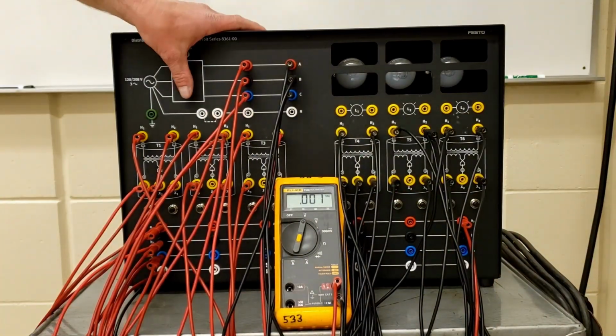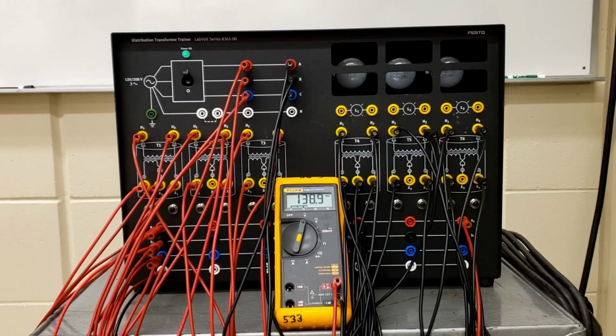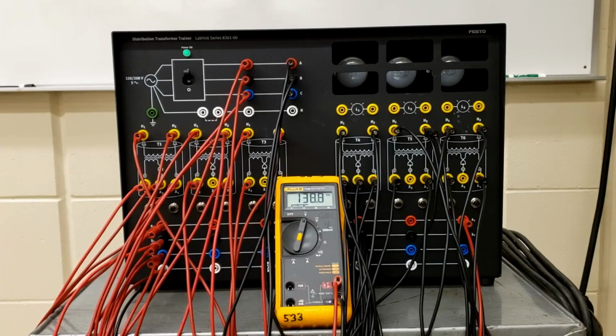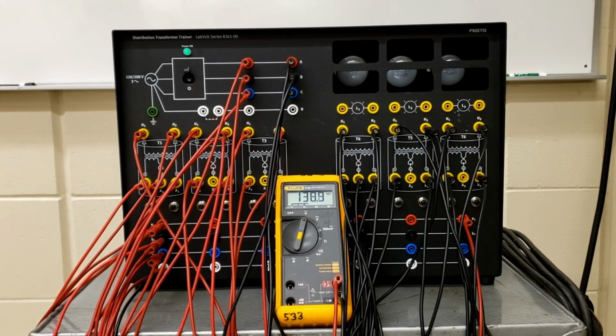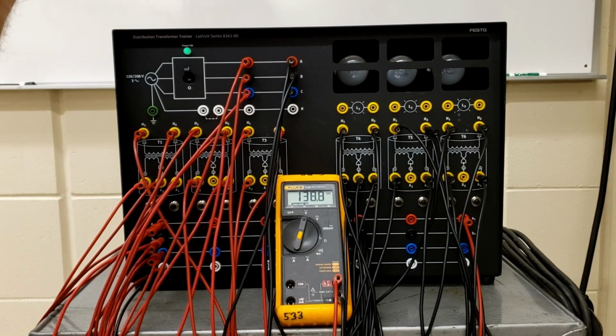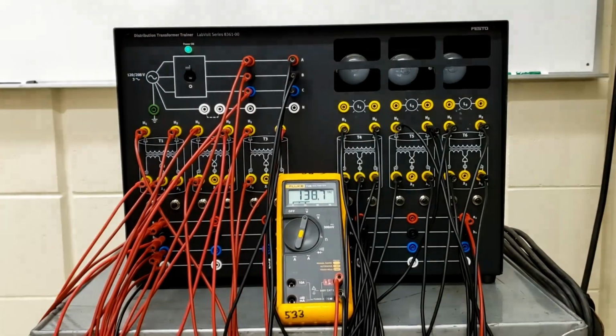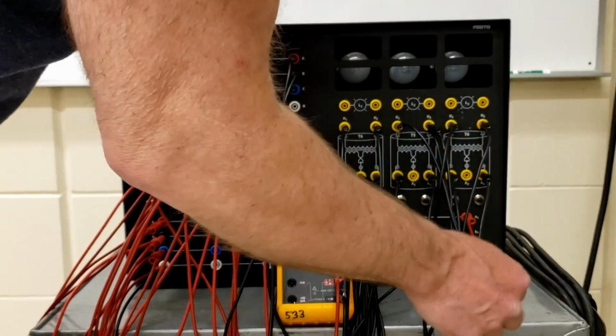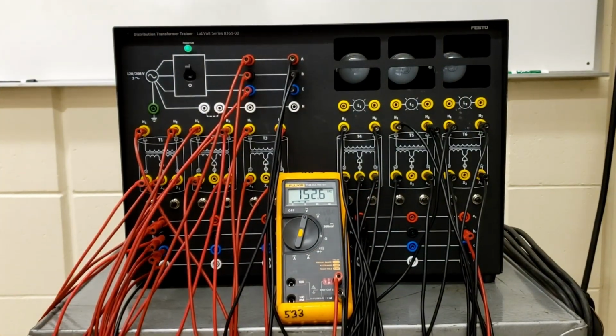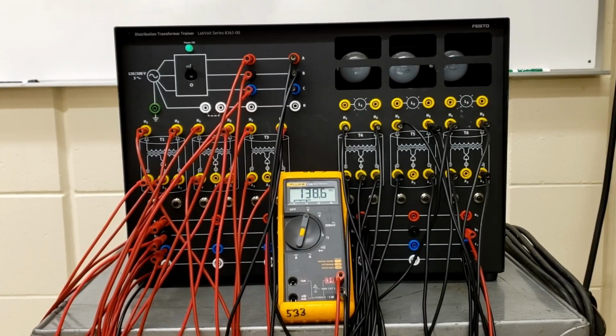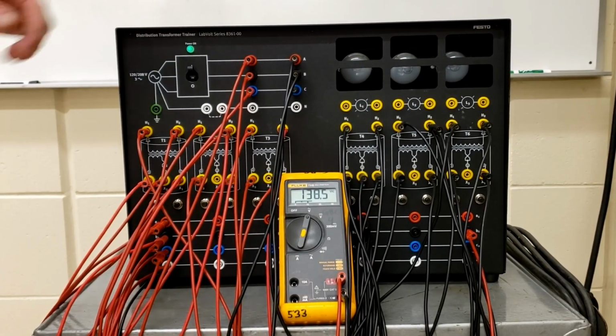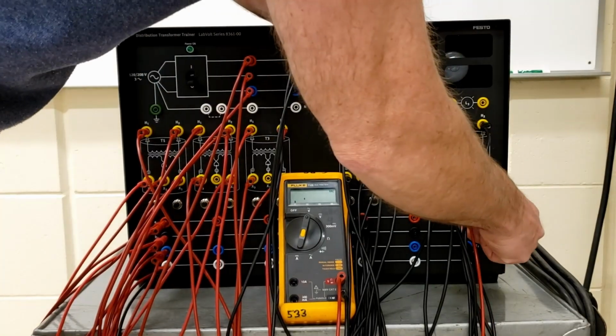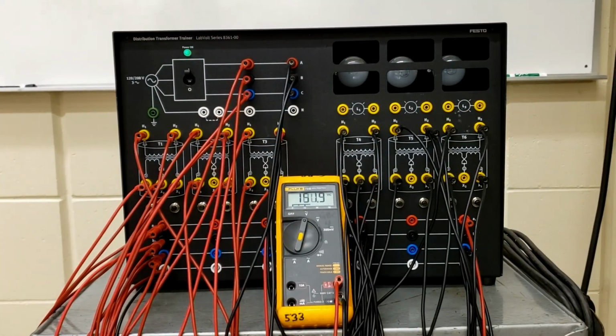Okay, so from A2 to B2 we've got basically 140 or 138 volts. We should have identical voltages all the way through here. Let's turn it off and look at B2 to C2, we should have an identical voltage of basically 140 volts there, and we're seeing again 138. And then between C and A, we should also have 138 volts. Looks good, 138.9.